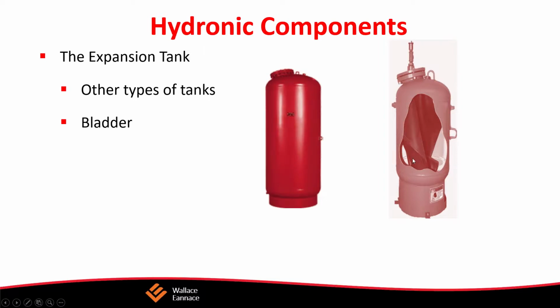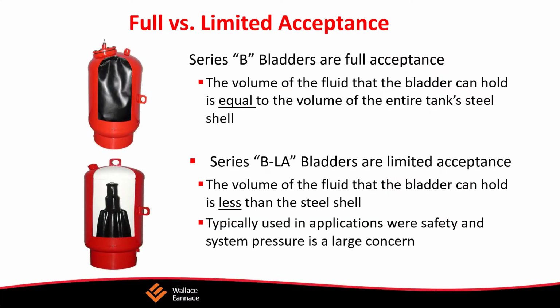So what does it do? If we raise the temperature of water in a heating system from 40 to 180 degrees, that adds about 5% more water simply by thermal expansion. The expansion tank's job is to absorb this thermal expansion. It provides a spring to maintain the minimum pressure set in the system. Keep in mind, unlike air, water does not compress.